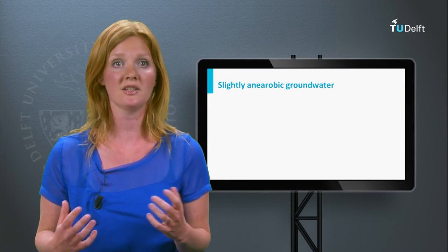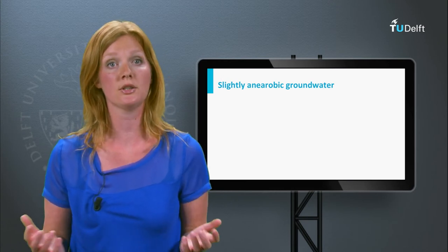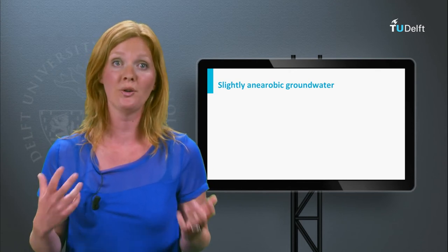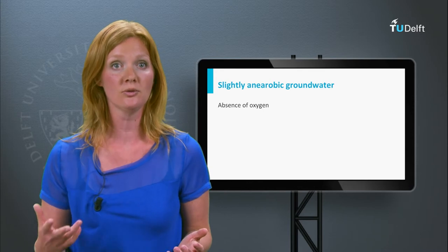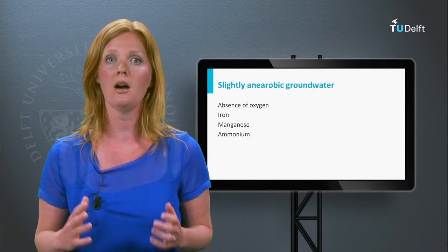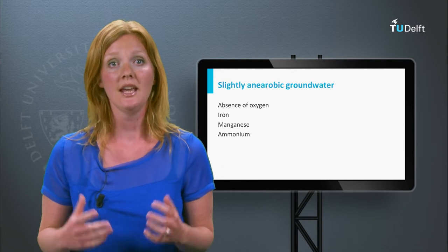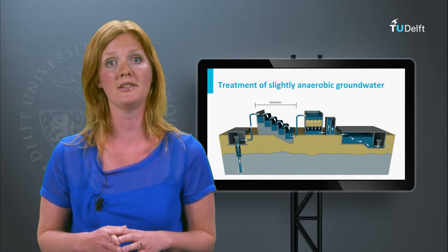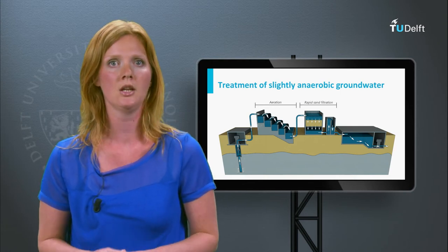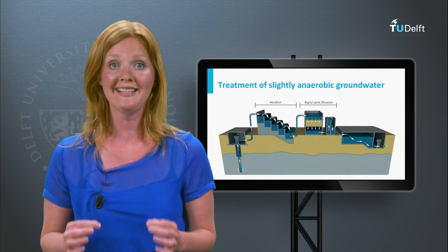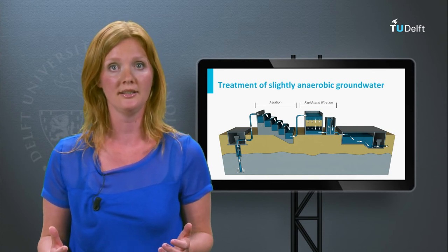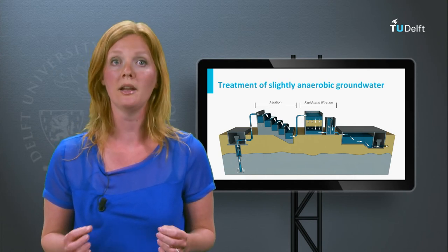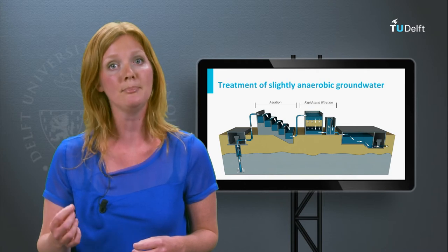The water treatment scheme for slightly anaerobic groundwater differs from the scheme for aerobic groundwater. Slightly anaerobic groundwater is located under a confining layer and is characterized by the lack of oxygen and presence of ammonium, iron, and manganese. In general, the treatment of slightly anaerobic groundwater consists of aeration followed by submerged granular media filtration. Aeration is needed for the addition of oxygen and the removal of carbon dioxide. The oxygen is used for the oxidation of ferrous iron (Fe²⁺) to ferric iron (Fe³⁺).